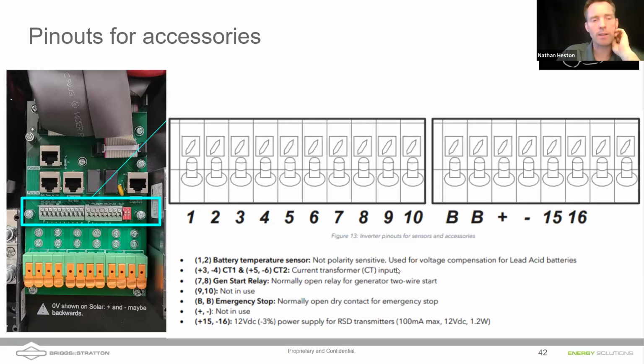And then the CTs. Now, I have heard that we should still use the CTs for the Sol-Ark 15Ks if we want increased accuracy on power coming from the utility. Is that the recommendation? No, that's exactly correct. Yeah, okay. Even though Sol-Ark has an internal CT, the CTs provided, and they're shipped in every package, provide some additional functionality around limited power to load, around time of use settings, and in general accuracy. So we always recommend that you install those, even if you're passing through the entire 200 amp service through a 15K. And I believe you said that the 12K comes with 100 amp CTs included in the packaging, and the same thing with the 15K coming with 200 amp CTs. That's correct.